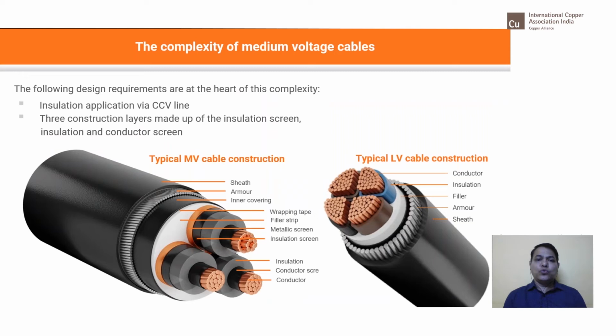This is how the two cables look. You can see on the left side a medium voltage cable construction with the circular copper conductor, whereas the low voltage cable can be a sector cable with a sector shaped conductor. The medium voltage designs are more complex than their low voltage counterparts, as they are used in critical applications and are relied upon for safety in the transportation of energy. Both the processing and the structure are totally different to LV cable to ensure that the required end user applications and performance requirements are met.